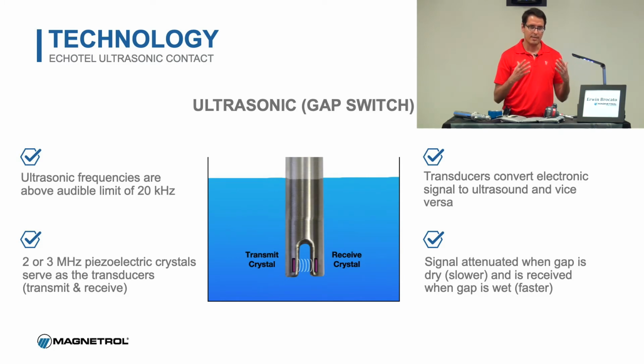Basically all it is, it's a switch that cares if the probe, the gap that you can see on this image here, is wet or dry. That's all it cares about. It doesn't care about dielectric constants. It doesn't care about changes in specific gravity. It can be a low specific gravity. It can be a high specific gravity. None of that matters. The only thing that matters is if that probe is full with liquid and the ultrasonic signal can transmit in between the transmitter and receiver, your switch, the relay will be energized.